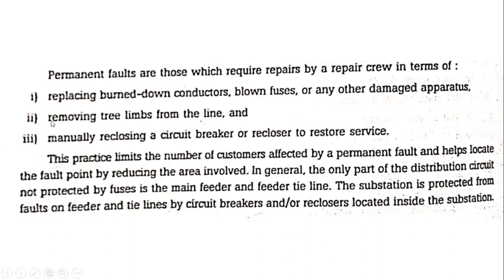Permanent faults are very rare faults, and temporary faults are very common, up to 75 to 90% of faults. Due to temporary faults, there is no high risk for the distribution systems or the protection systems.